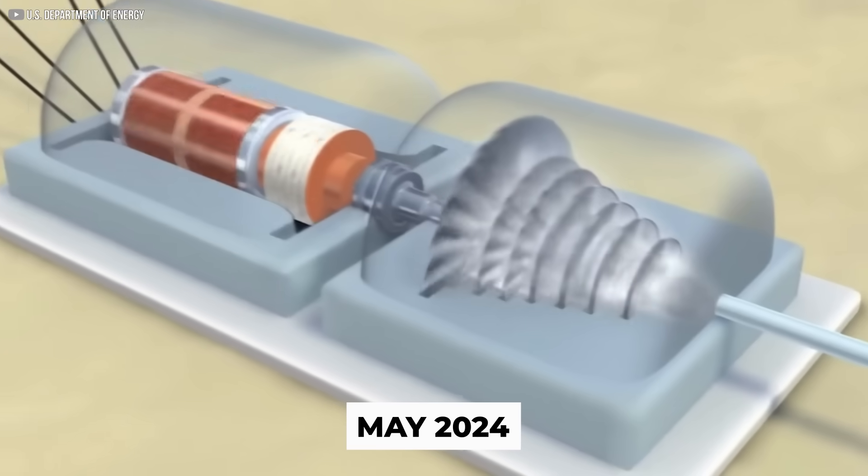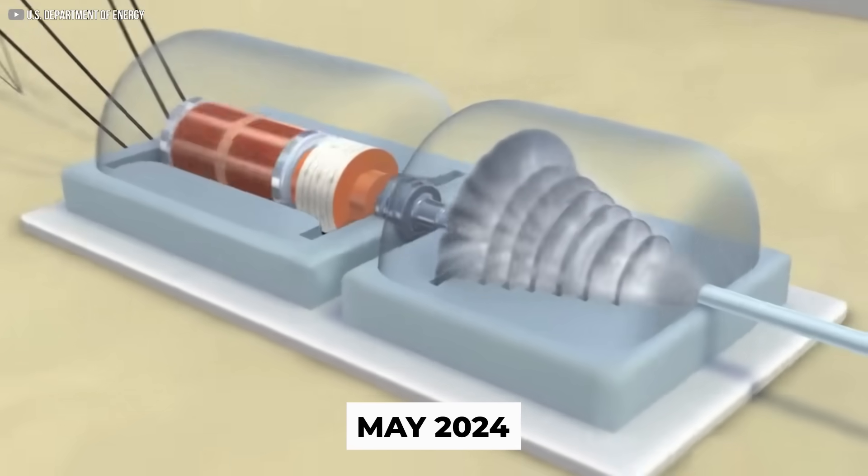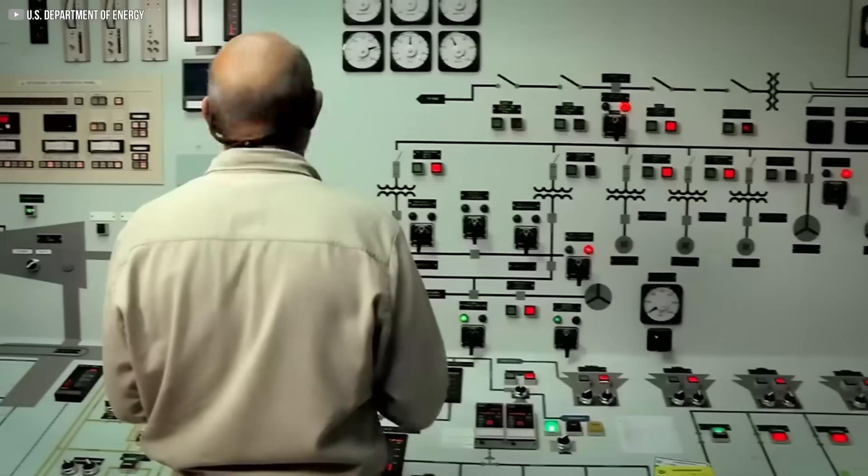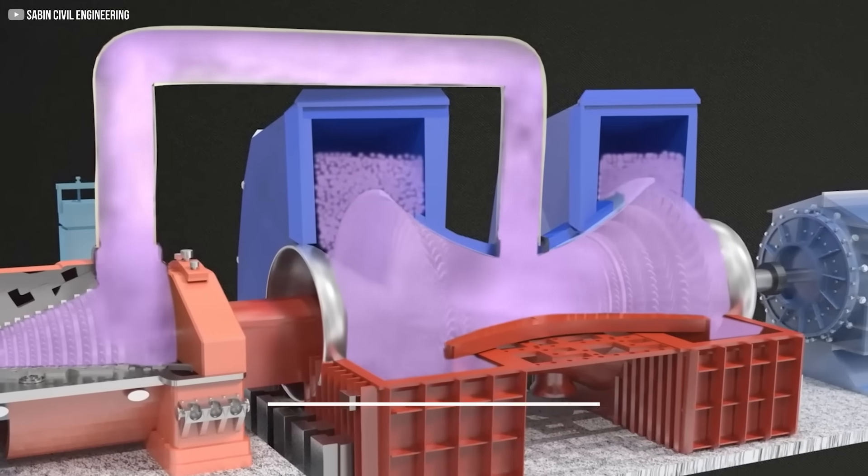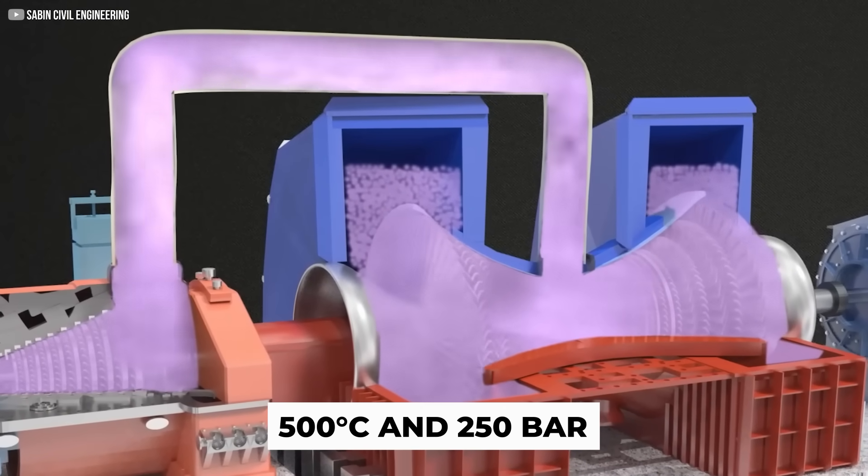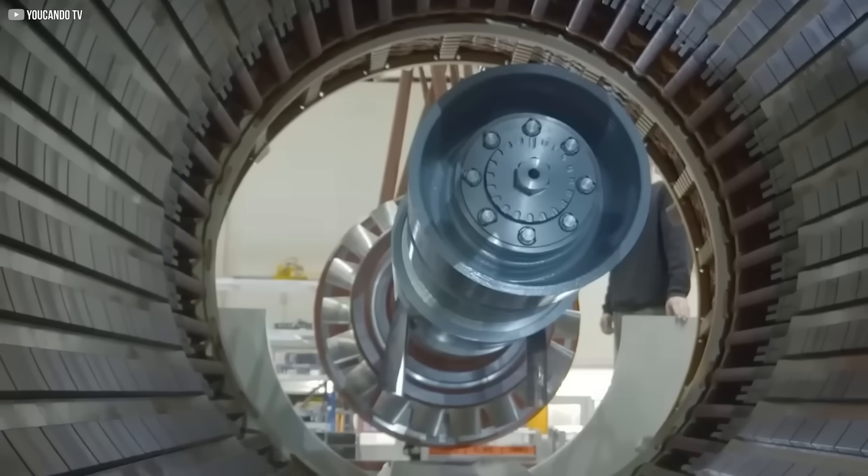By May 2024, the plant successfully produced electricity, generating four megawatts of grid-synchronized power. The turbine reached speeds of 27,000 rpm at an operating temperature of 500 degrees and 250 bar. This project highlights the practical possibilities of supercritical CO2 systems, showing that they can work in real-world environments.